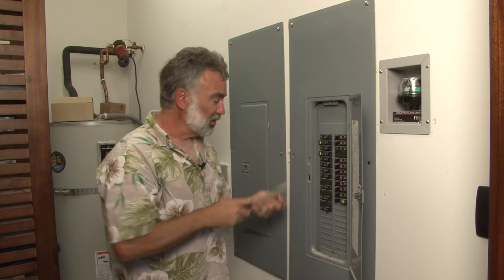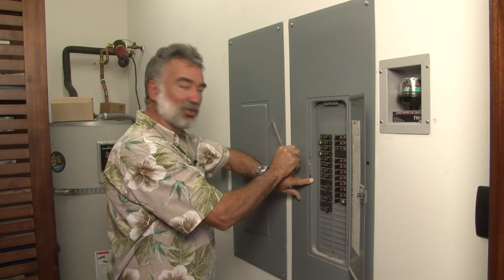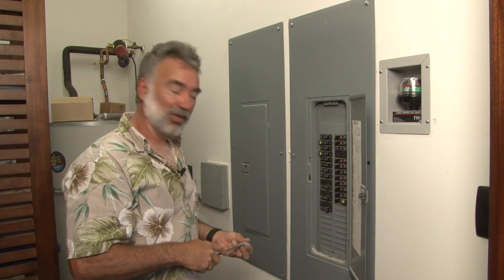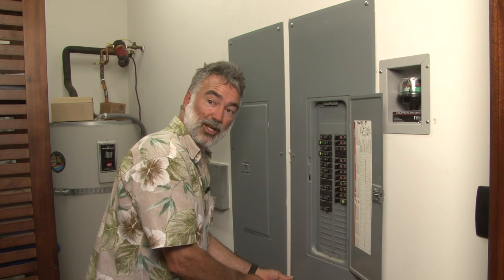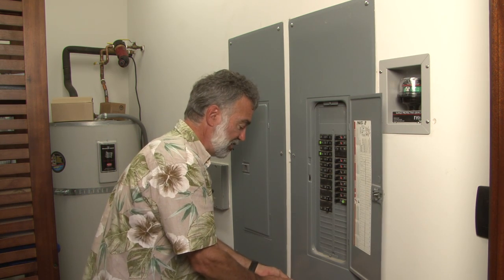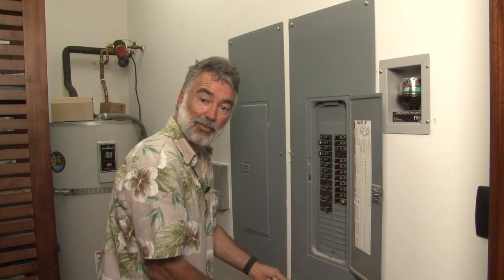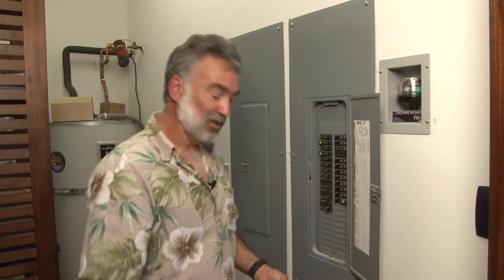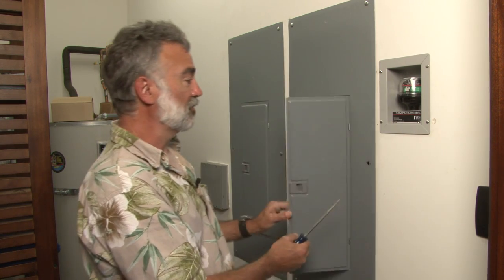The thing with lightning surge arresters is you can't really ever have too many of them. Ultimately, you would have one at your service entrance out at the street or where the utility comes into your house. It's a good idea to have one at your distribution panel like this. And if you have any other subpanels that are more than 100 or so feet away from these panels, it's not a bad idea to put one out there also — it just protects the whole system from induced surges coming in from any other direction. I'm Tom Carpenter from MidNite Solar. Thank you very much.